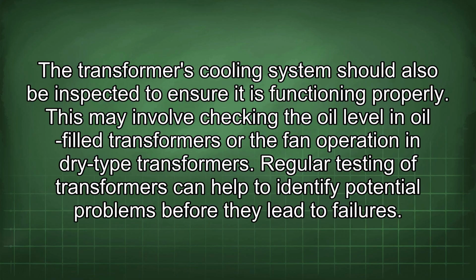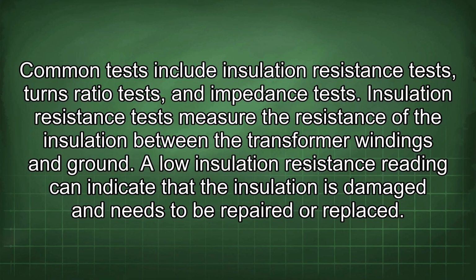Regular testing of transformers can help to identify potential problems before they lead to failures. Common tests include insulation resistance tests, turns ratio tests, and impedance tests. Insulation resistance tests measure the resistance of the insulation between the transformer windings and ground. A lower insulation resistance reading can indicate that the insulation is damaged and needs to be repaired or replaced.